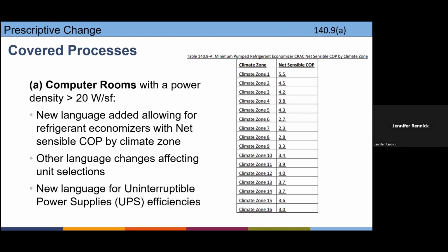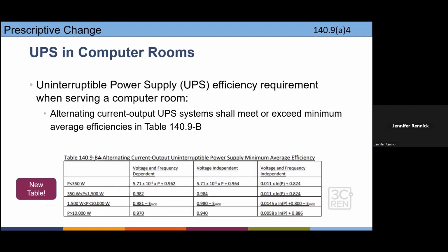When it comes to the computer rooms, same again: greater than 20 watts per square foot. And there's some new language on it and new efficiencies in COP, coefficient of performance, based on climate zone on the equipment. So that part's new. Same kind of idea. Now we're dictating efficiencies on the UPS, or uninterruptible power supply, for all that equipment. So there's a new table, and these are now based on your connected load rather than climate zone.